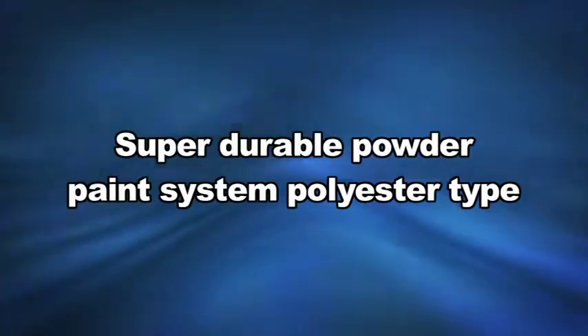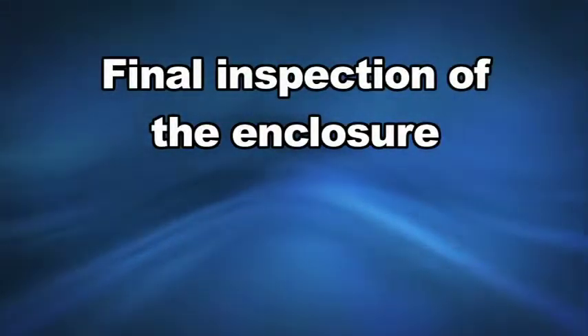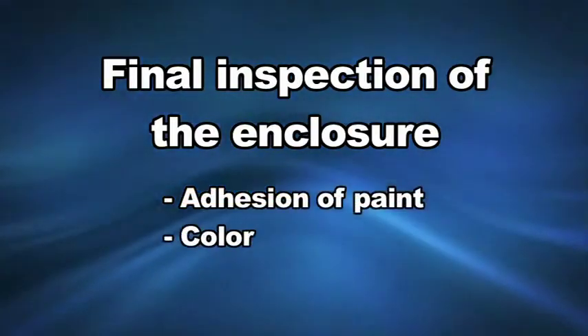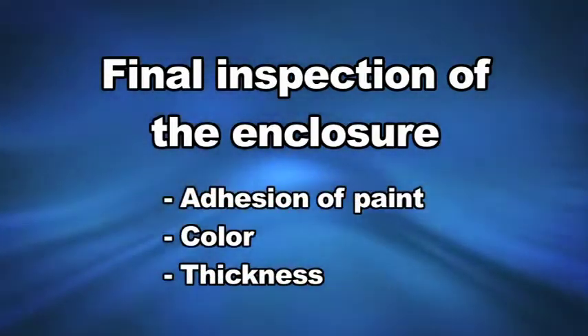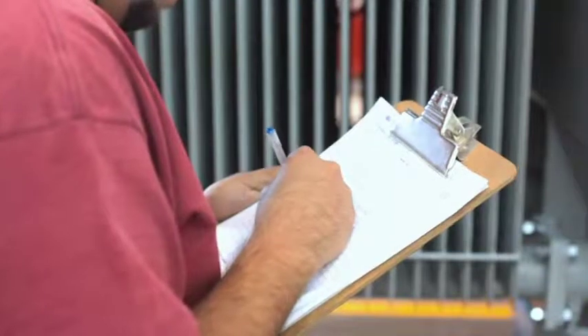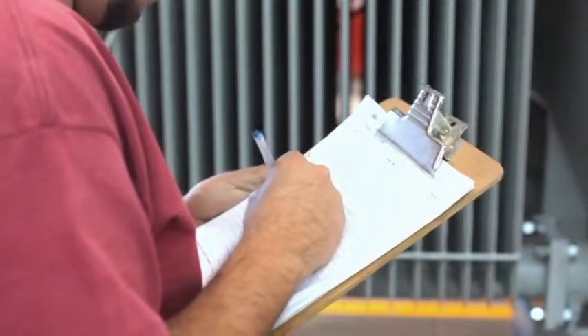It is worth mentioning here that a super durable polyester type powder paint system is used, which is applied to the enclosures with an electrostatic system and then put in a curing oven at high temperature. In the final inspection of the enclosure, the adhesion of paint, the color, and the thickness are checked, as well as the compliance with all requirements and details that the mechanical drawings show.